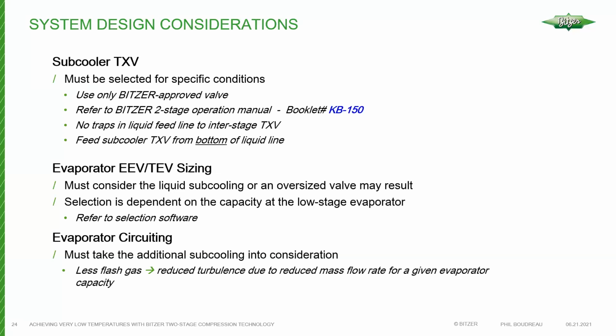No traps in the liquid feed line to the Interstage mixing valve, or the Interstage TX valve rather. As I mentioned before, this provides Interstage cooling, which is critical. It's very important that it has the best quality liquid available in that system. So you always want to come off the bottom of the liquid line. And if you've got existing systems in the field where you find that the superheat is very hard to control, or it's high and then it's low, and I mean, you can evaluate valve size and things like that, but take a look at the way it's piped.